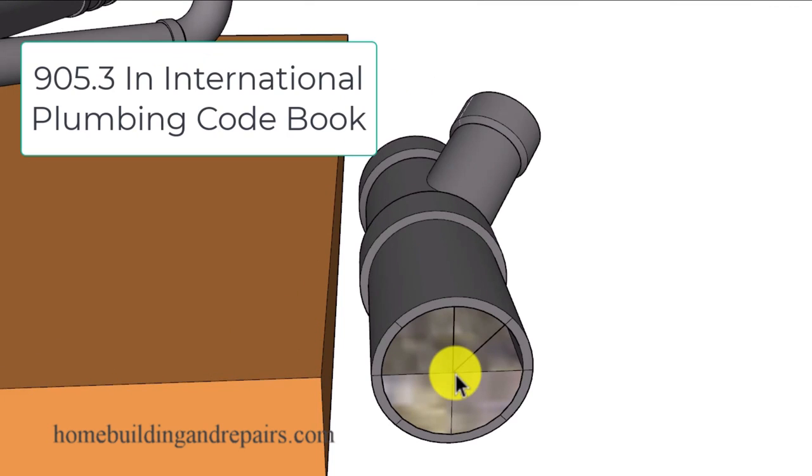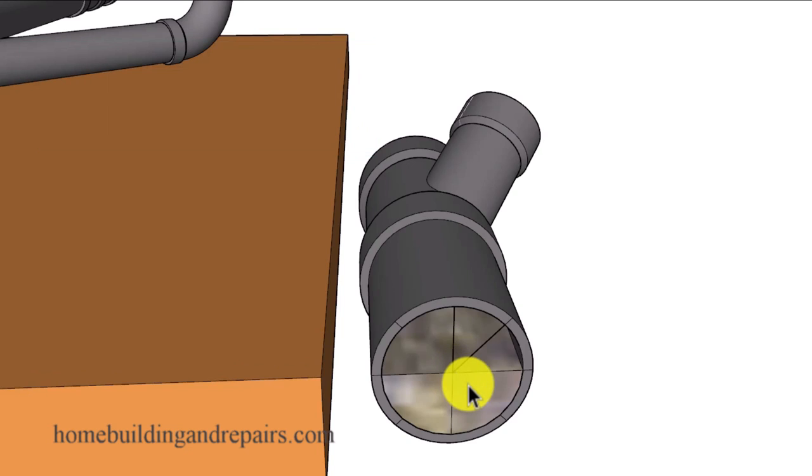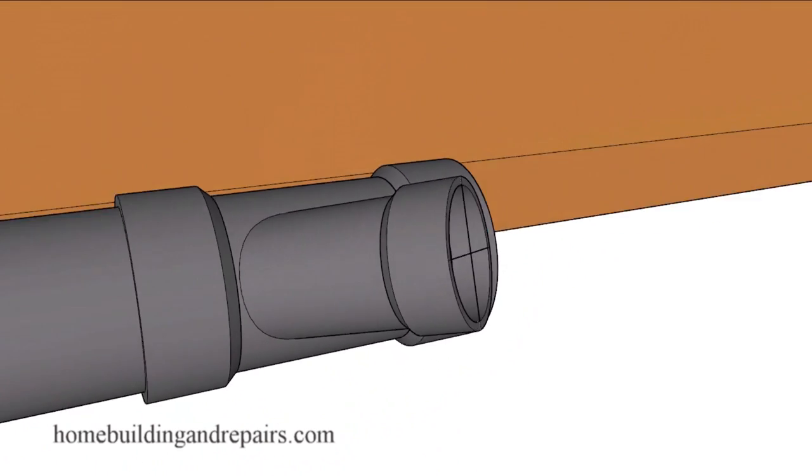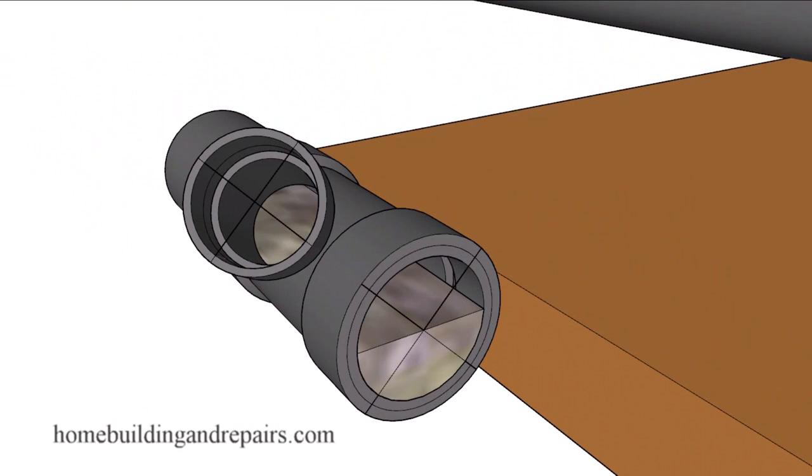And the building code says that dry vents connecting to horizontal drain pipes shall connect above the center line of the horizontal drain pipe. And almost all of the plumbers that I've worked with suggest that this means this pipe right here cannot be rotated more than 45 degrees from its vertical position. However, with that said, I've actually seen plumbers rotate these pipes a lot further. I've seen them rotated just barely off of the horizontal position. So you might want to check with your local building department to see if that will be allowed in your area or allowed under certain special circumstances.